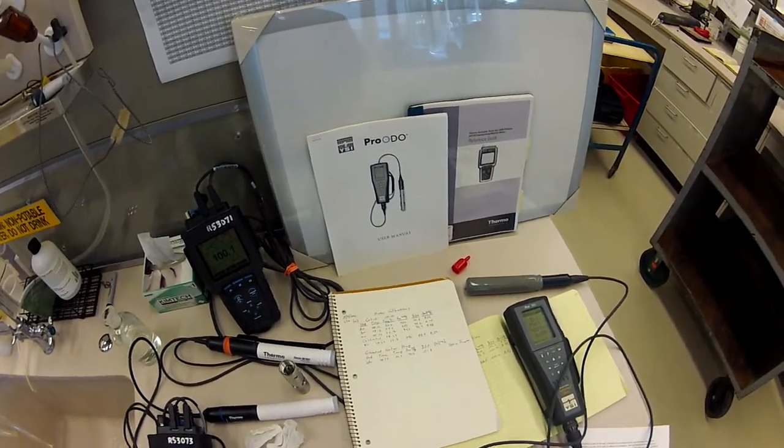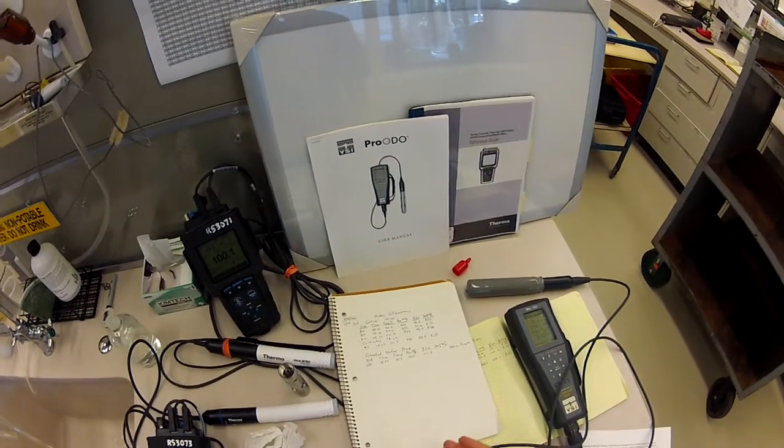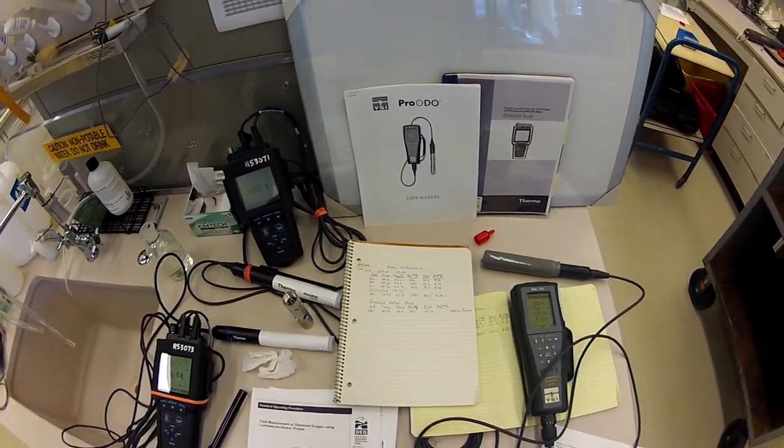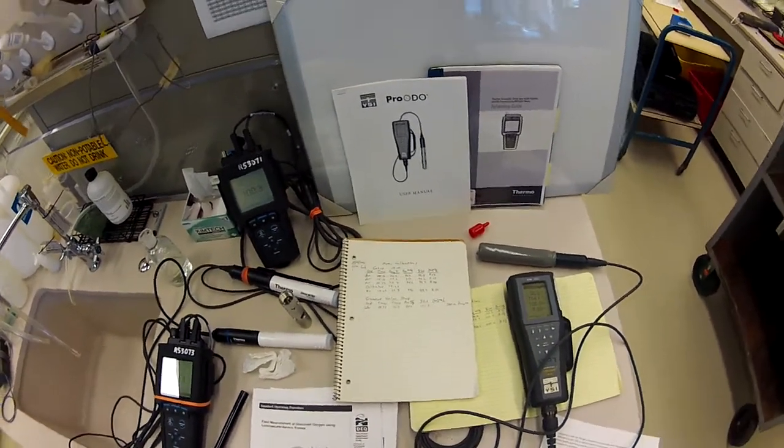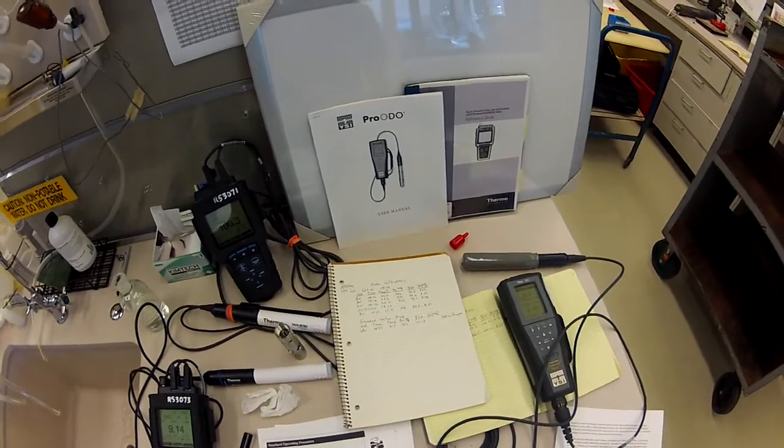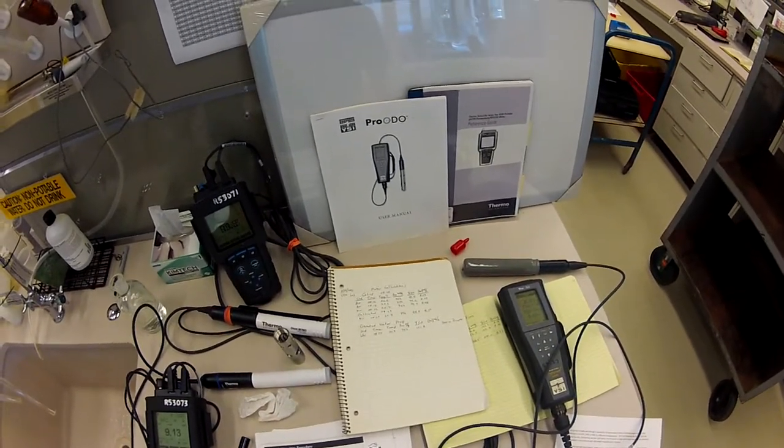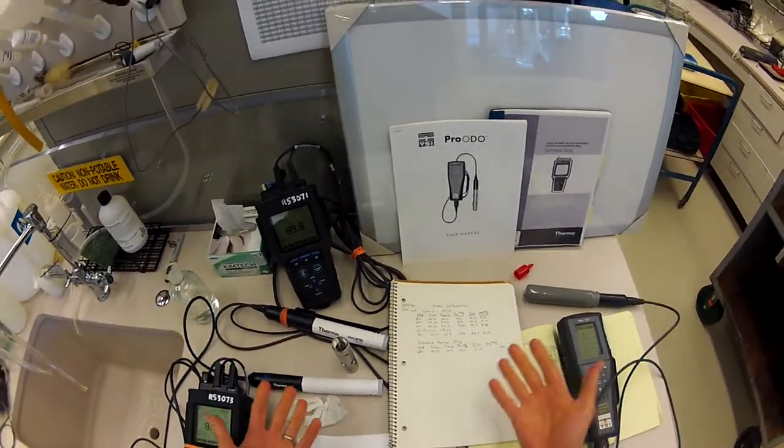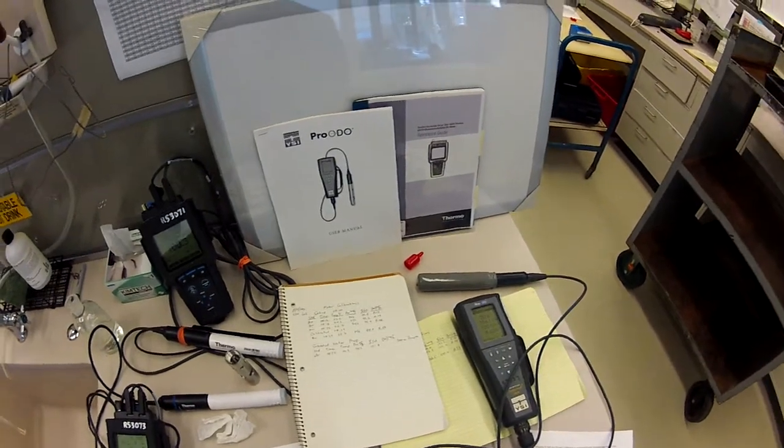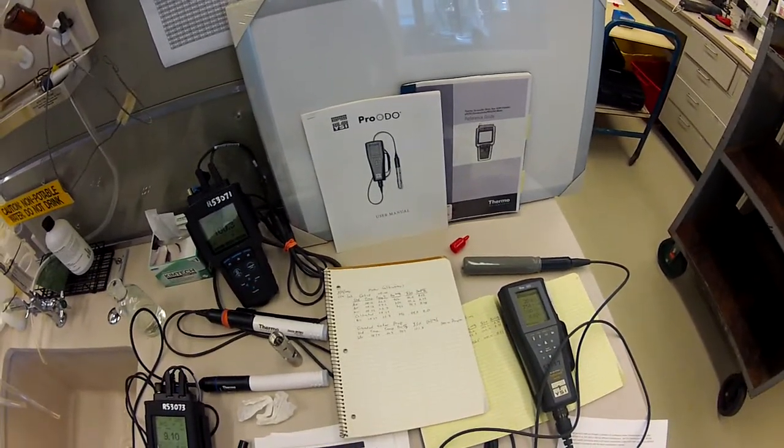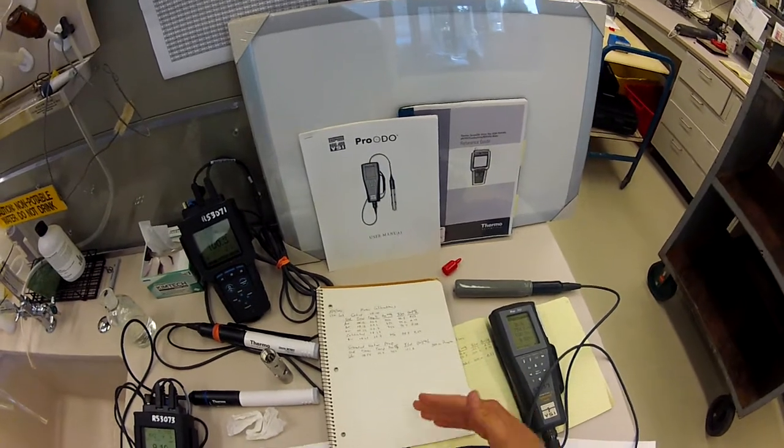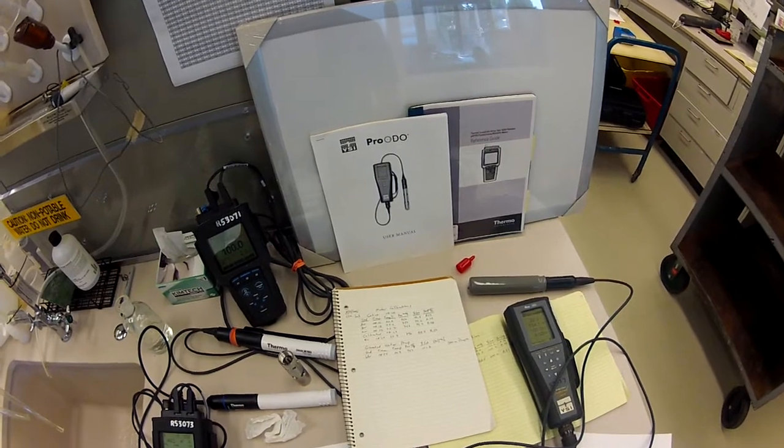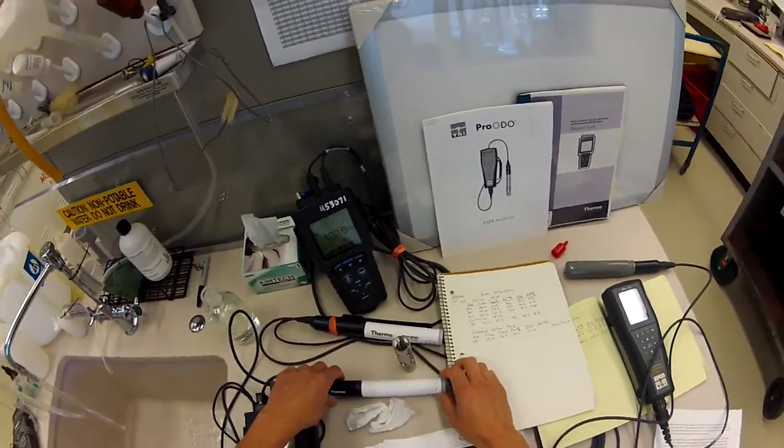So keep that in mind - be critical of your standard that you're creating. You're not pouring something out of a bottle that's some approved lot by NIST or something like that. With these calibration standards you're creating it yourself, so you need to think critically. And if you feel like the environment that you're working in is not giving you a stable environment like we have here in the lab, then maybe it's better to not recalibrate but to just try to do verifications and make sure that your initial calibration is still holding. With these LDO probes, they quite often do.